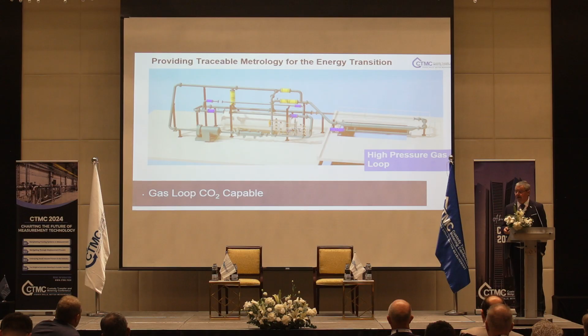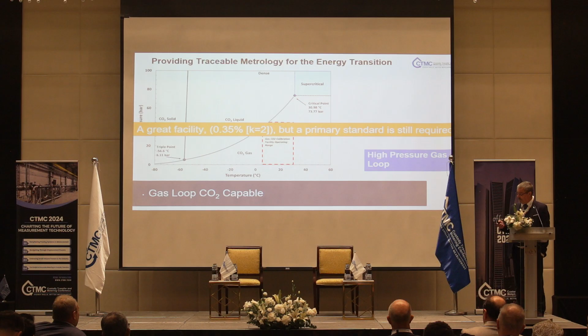We have our high-pressure gas loop, which we have repurposed now. We can take out the nitrogen, put in CO2. And that's quite useful, we think, because the facility range coincides with a lot of the gas pipeline that we saw earlier in the presentation. So it's fantastic. It's a great facility, 0.35%, almost 10 times better than the 2.5% requirement for the ETS, but it's not a primary standard. It still uses reference meters which are calibrated elsewhere.